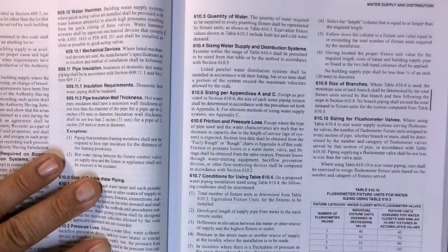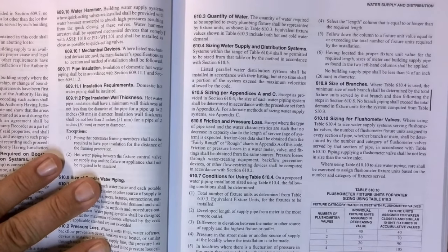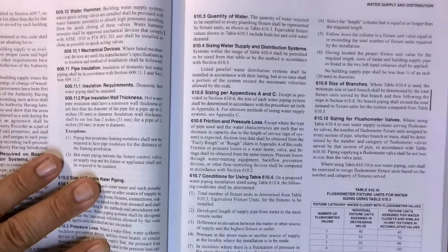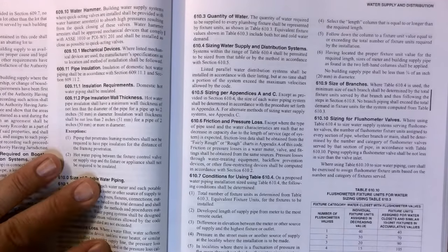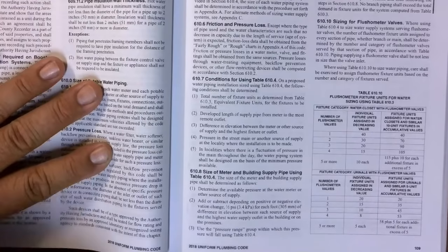Section 610.6, friction and pressure loss. Except where the type of pipe used and the water characteristics are such that no decrease in capacity due to the length of the service is expected, the friction loss data shall be obtained from the fairly rough or rough charts in Appendix A of this code. Friction or pressure loss in a water meter, valve, and fittings shall be obtained from the same sources. Pressure loss through water treating equipment, backflow prevention devices, or other flow restricting devices shall be computed in accordance with Section 610.2.